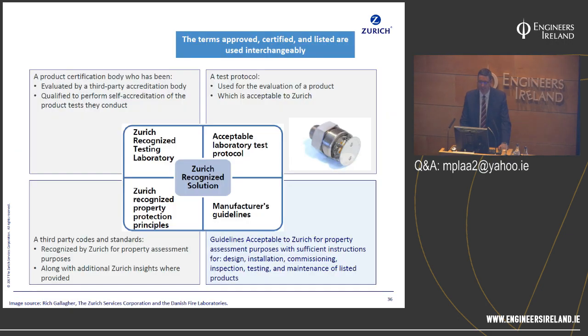However, how did we get to that point? We got to that point by undertaking fire testing at an approved lab by the fire test lab, using listed components that had been fire tested to a recognised global standard, in this case CEN 14972, and we also had detailed manufacturer's guidance. Now when I get water mist systems for these type of applications, I go through this 4-stage process, and at the moment there is no manufacturer in the world, apart from one, who have undertaken this form of testing for combustible saunas.